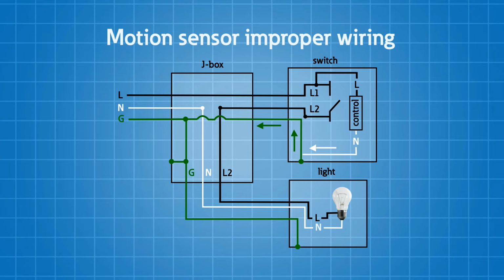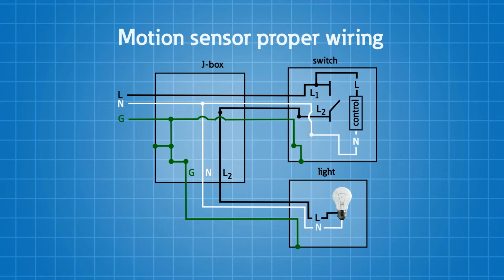And based upon the definition that we just created, that would be current flowing on the equipment grounding conductor that's not because of a faulted condition. That would be what we call objectionable current. And that is not permitted by the National Electrical Code. So changes have occurred over the last few cycles, one, to prohibit the use of those products, and two, to require the pulling of a neutral at those switch locations. So in case you installed a technology that required to be powered up, you're not likely to grab that equipment grounding conductor to get that done. You will properly use the neutral grounded conductor to get that done. So hopefully that helps you understand what we mean by objectionable currents. And remember, all of these terms that we just talked about, it's critical that we use these terms correctly as we communicate to make sure that we all understand each other and we get things right. And hopefully this little review helped you.